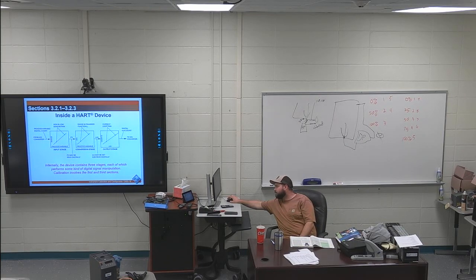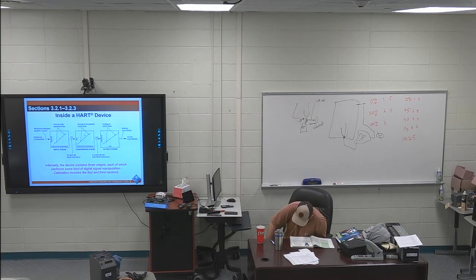Your factory characterization is what happens in the middle stage, and that's what you never want to change. You don't want to change how this thing does the math and calculations in order to make an output. Calibration involves the first and third sections, never the second one. Top right of page 21, the last sentence of that started paragraph in the top right. Conversion of the analog process signal to a corresponding digital equivalent prior to being sent to the second stage is done by an analog to digital converter, ADC, in the processor.